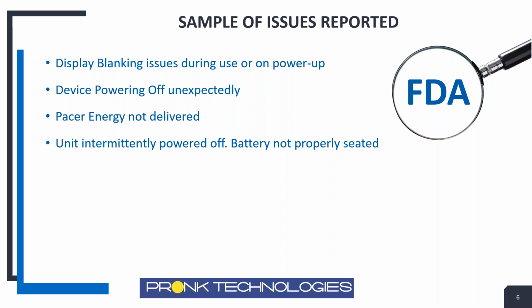I wanted to add it here because it was intermittently powering off in clinical use, and the manufacturer did investigate it, did post it on the FDA website, and they found that the battery was not being seated properly in the device. It seems like a simple but important thing to take note of, and it's important to understand that sometimes it may not be as complex an issue as you would think. In this case, critical but important, the failure that occurred was that the battery was not seated properly.